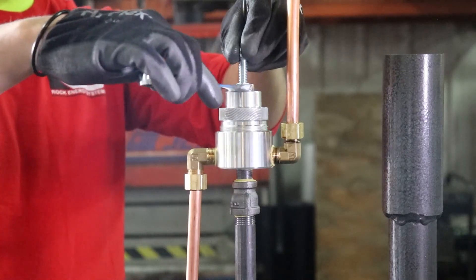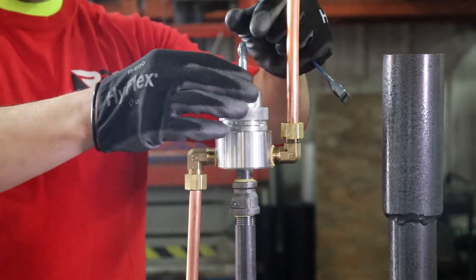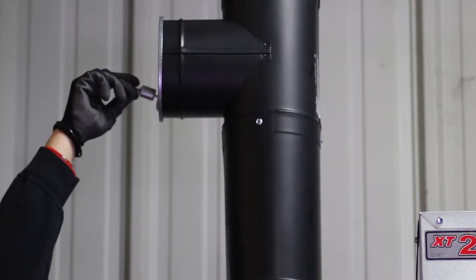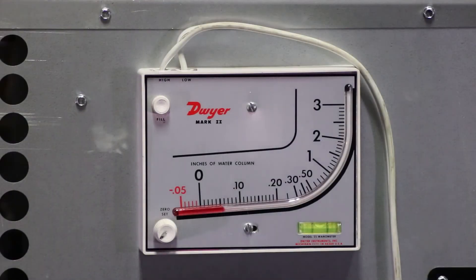Set the fuel oil pressure based on the product manual's recommendation for your model. To do this, loosen the locking nut on the oil pressure bypass regulator and turn the thumbscrew to adjust the fuel pressure based on the gauge at the burner. Retighten the locking nut after making adjustments. Adjust the weight of the damper door until -0.05 inches of water column is achieved as read by a properly calibrated manometer.